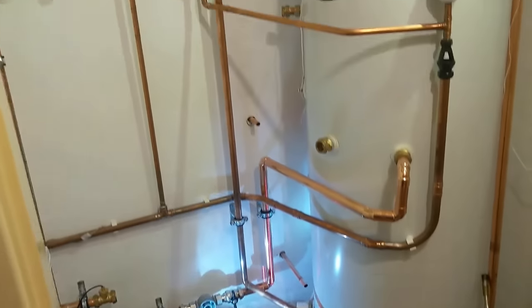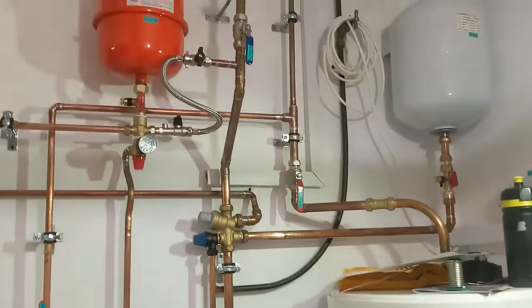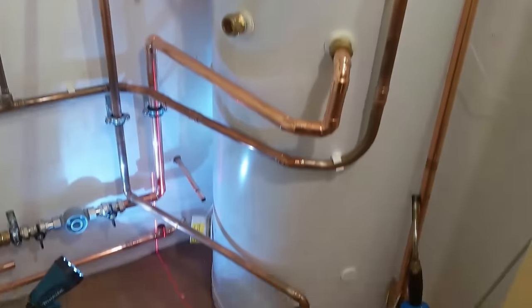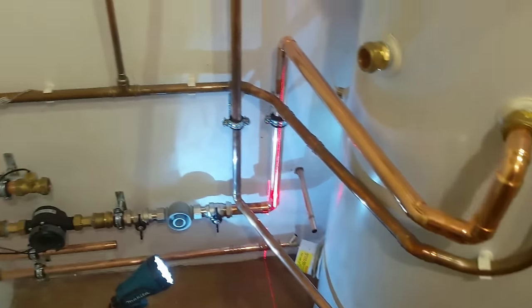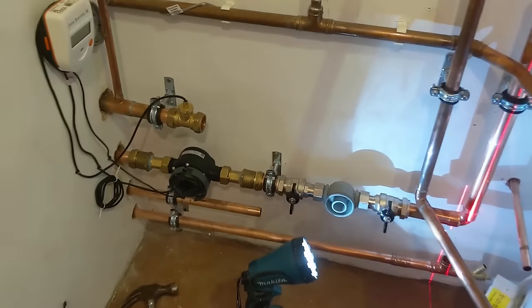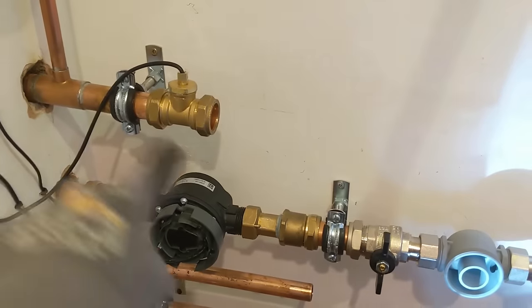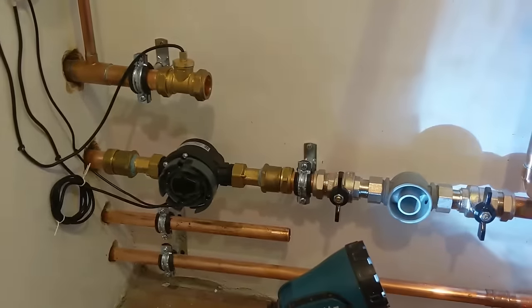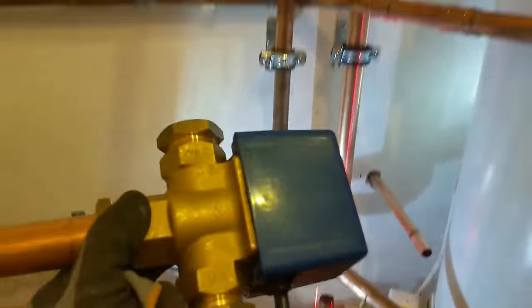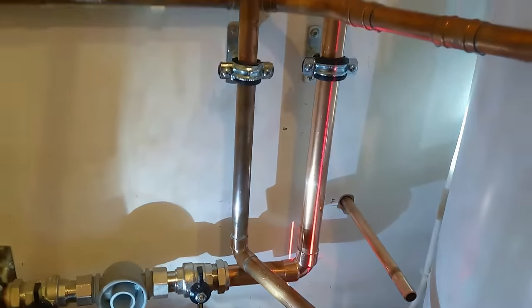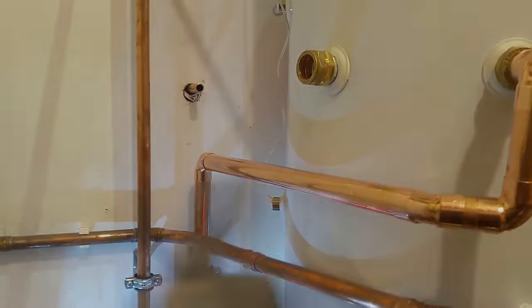So, making good progress here in the plant cupboard. Cylinder's all been up and running for quite some time now, so that's all good. I've now been starting on the primary pipework, so these are the two 28mm flow and return that go into the heat pump. So now I just need to do the flow and put the three port valve in, which will switch the flow between tank or central heating.